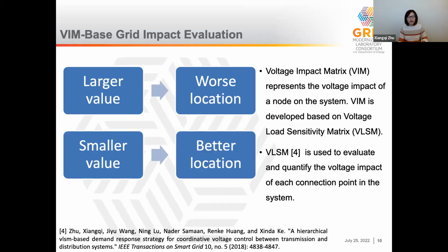To evaluate the grid impact caused by charging loads, we developed a voltage impact matrix, called VIM, representing the voltage impact of a node on the system. If a node has a larger VIM value, connecting a charging station there will cause more voltage fluctuation in the system.